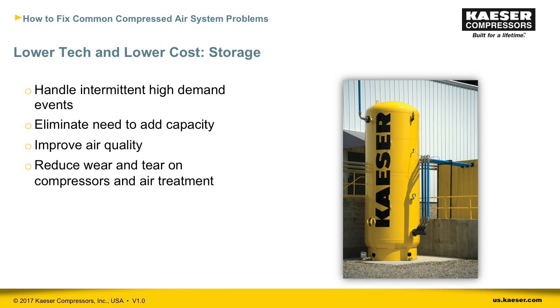On the lower tech, lower investment end of the spectrum, we can start off with compressed air storage. Adding in a properly sized receiver tank can benefit your system in a number of ways. If you have a part of your process that needs large bursts of air intermittently, you can use a tank to supply the extra air instead of adding another compressor. Tanks also improve air quality and reduce wear and tear on compressors and air treatment.